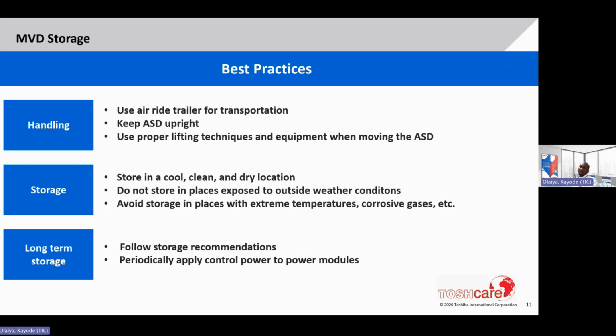Now to storage and startup. As I mentioned, maximizing drive performance starts from how it is stored and handled. It's important to follow best practices for transportation, for storage, and long-term storage, making sure you use an air ride trailer for transportation so components are not damaged or jarred loose before even getting to site, making sure the drive is kept upright at all times, and using proper lifting techniques when moving the VFD. Dropping a VFD will not be a good way to maximize drive performance.